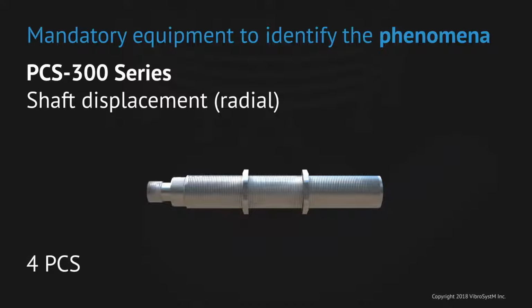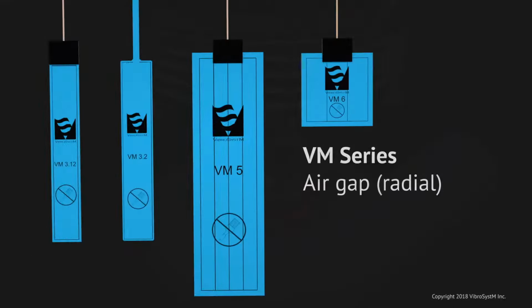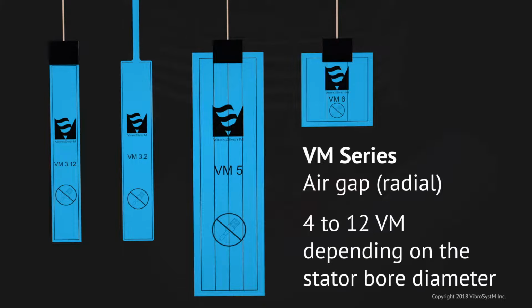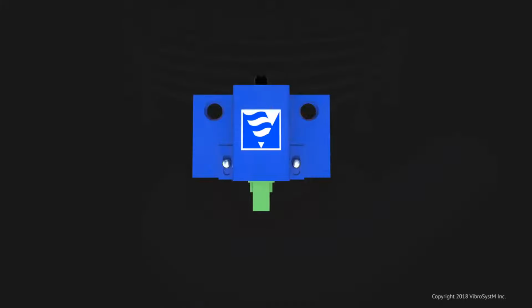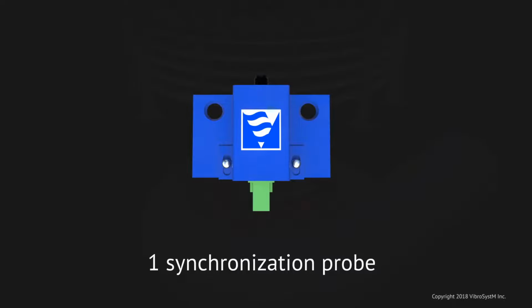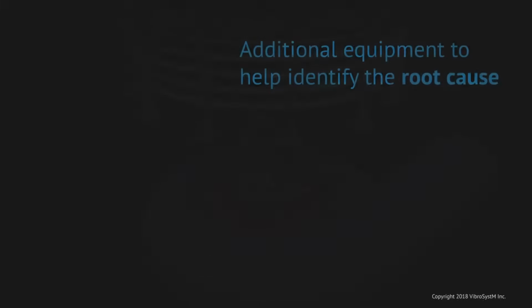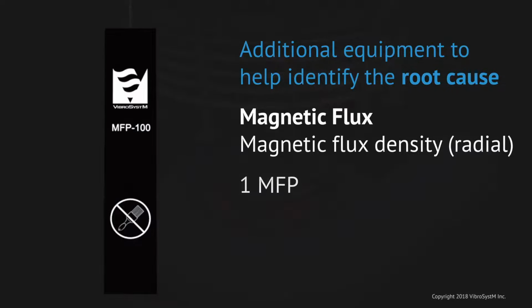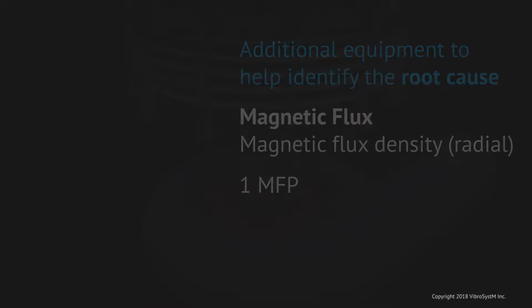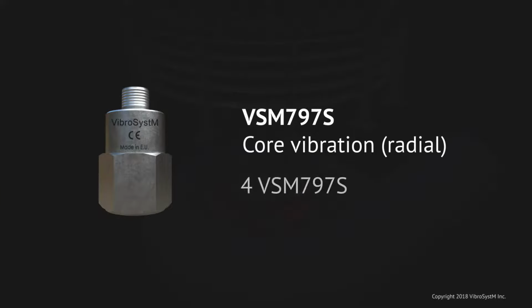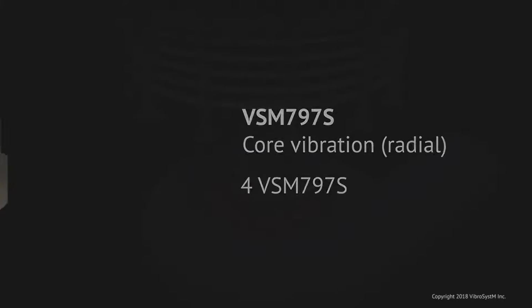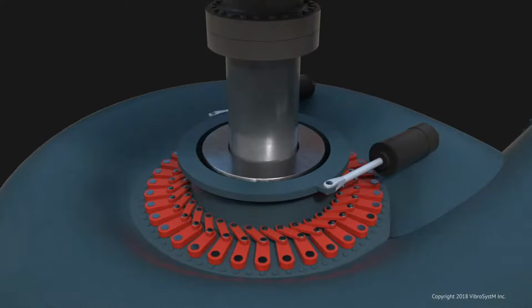Well, shaft displacement probes are always very important to see how much the rotor is moving. You need the air gap probes to be able to tell what the rotor shapes and positions are. The synchronization probe tells us where we are, where the poles are. And in some cases, there's additional equipment to help identify the root cause, such as magnetic flux probes, core vibration accelerometers, and so forth.